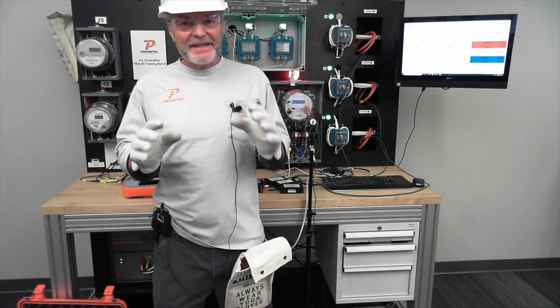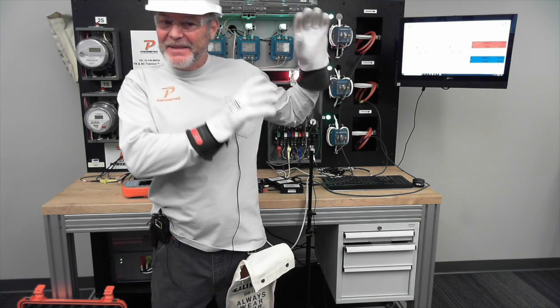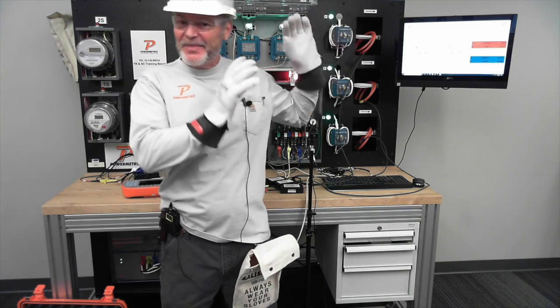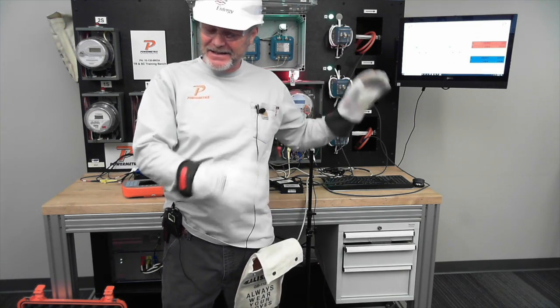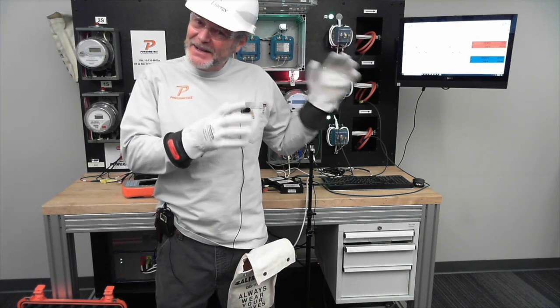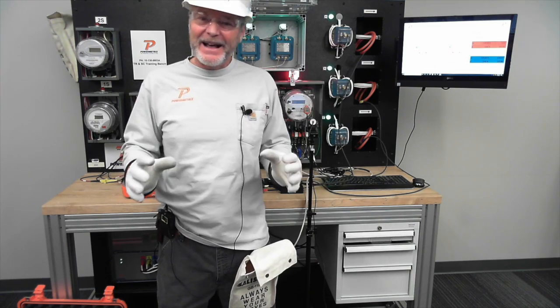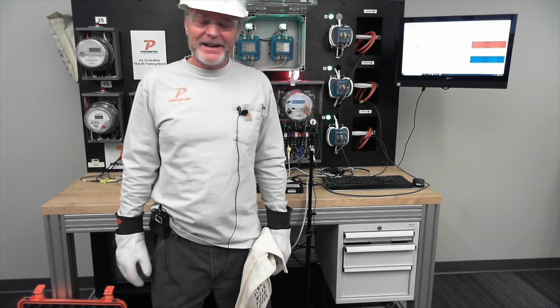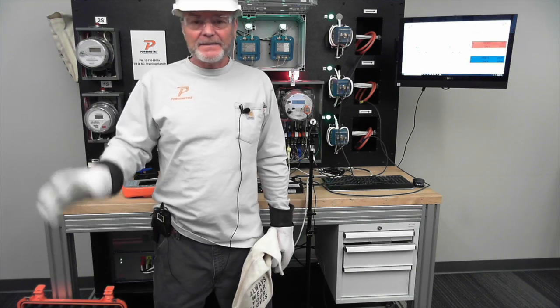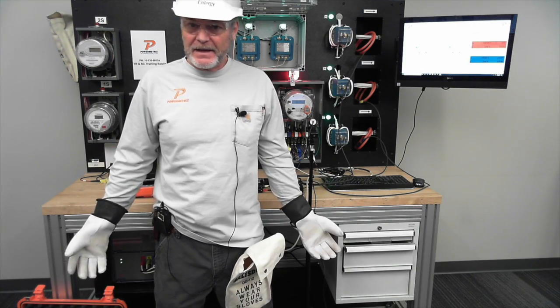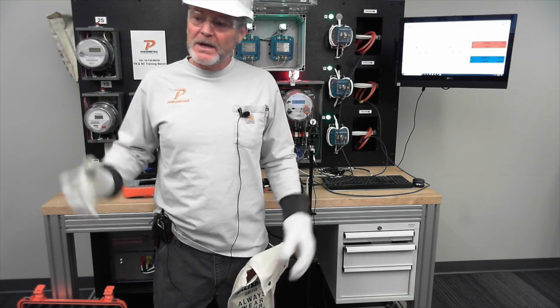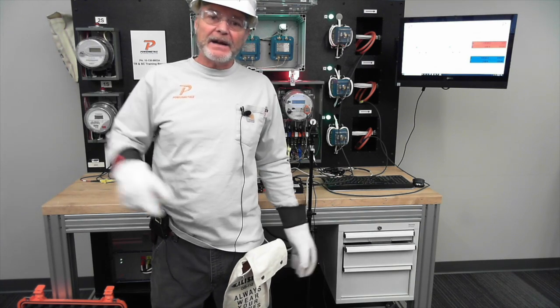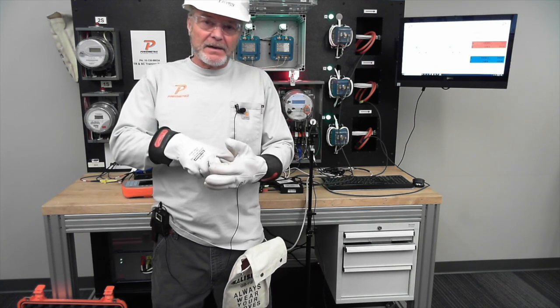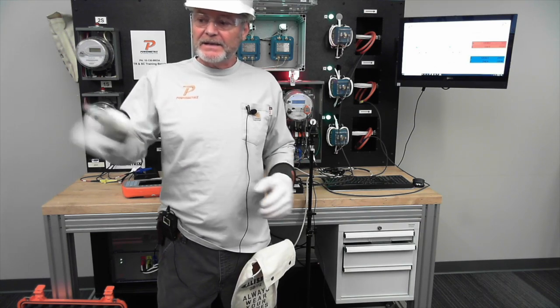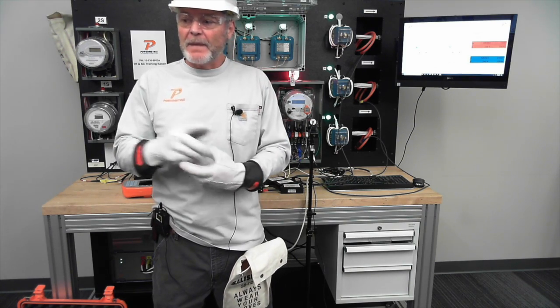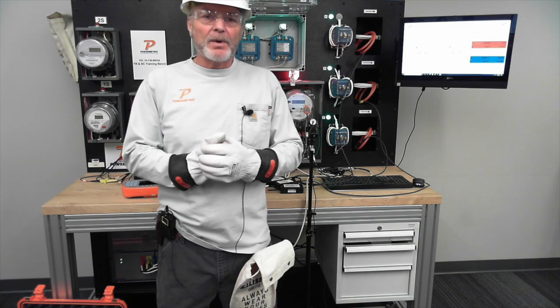They sure didn't think about us when they built that pole, when they put that installation in. They do not think about the folks that have to test it. If they had just thought about us a little bit, they could have made it a whole lot easier on us. But it usually isn't that way. So that's why you need these probes, because we're going to run into squirrely stuff out there that doesn't fit the normal mold. We need some of these additional probes, and having that second probe channel allows us to do that. So we can still test stuff even when they throw us curve balls, just by adding a few of these additional probes in.